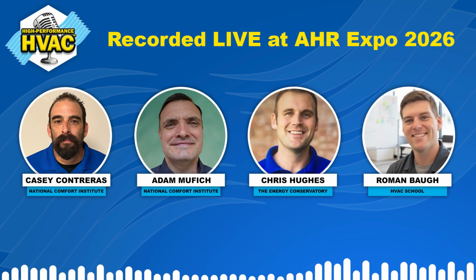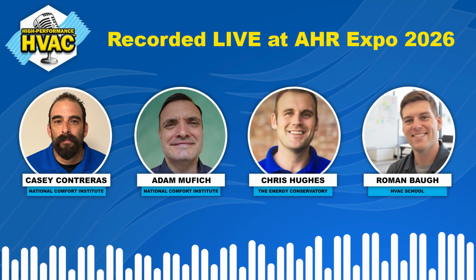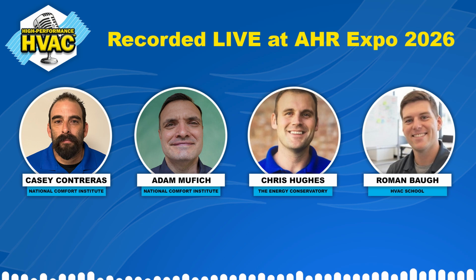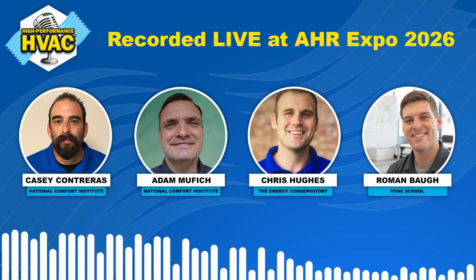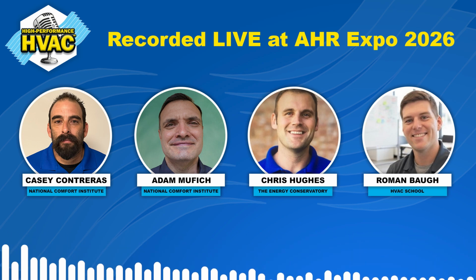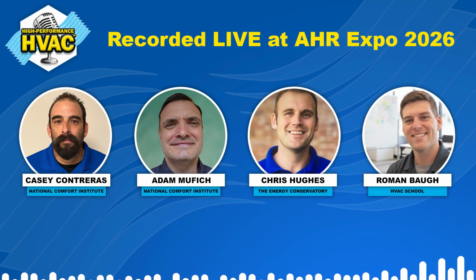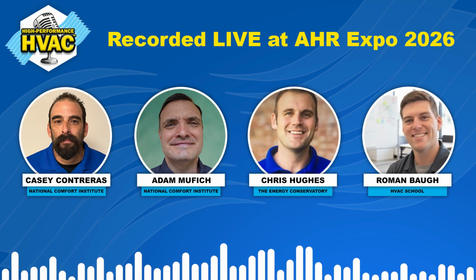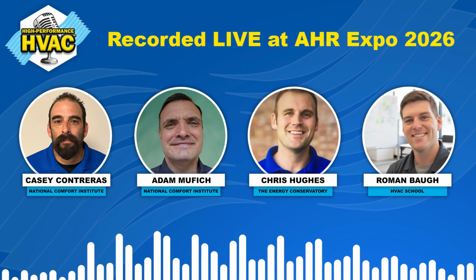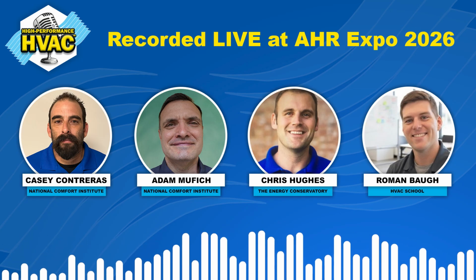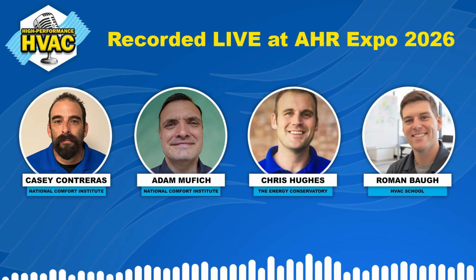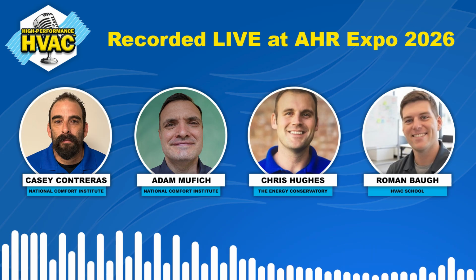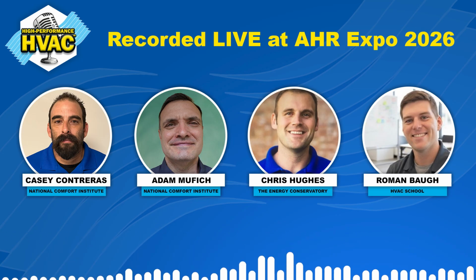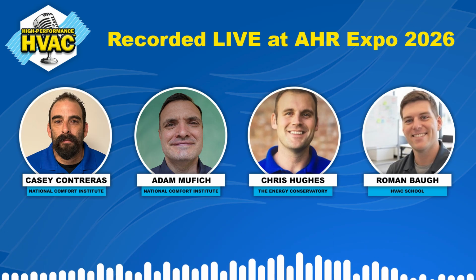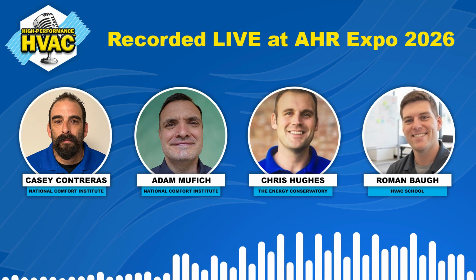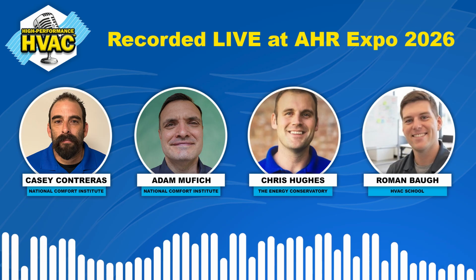Yeah. And there's workarounds. We could tent over the unit, put a heater in there, and heat it up. But that is adding some major complexity to the repair. It's not easy. So you'll see a lot of these commercial VRF guys that do a lot of this stuff in Canada, where that's just every day. And they got the whole setup, gas-fired heaters. They've got their gas tanks. They've got to get everything fired up. They tarp it. They tent it. They put up fake structures. They do all this just to pull gas to change a compressor out in the middle of a snowstorm, or even when it's 8 degrees outside.